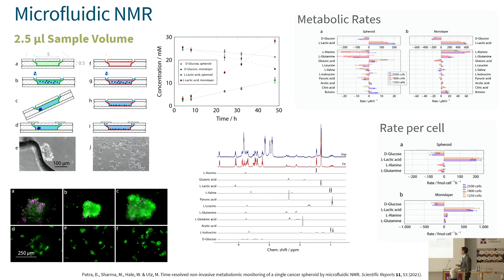So this is based on a strip-line type probe, which you see here. This is an NMR probe that just replaces the standard 5 millimeter probe that you may have in your spectrometer. And it's based on a strip-line geometry, which is a slight variation of the geometry that has been pioneered by the group of Arno Kentgens, in that we use two of these strip-line geometries. We put them with a spacer next to each other. So the sample then is in a microfluidic chip, which is designed to have its sample chamber aligned with the constriction, and that gives us high sensitivity.